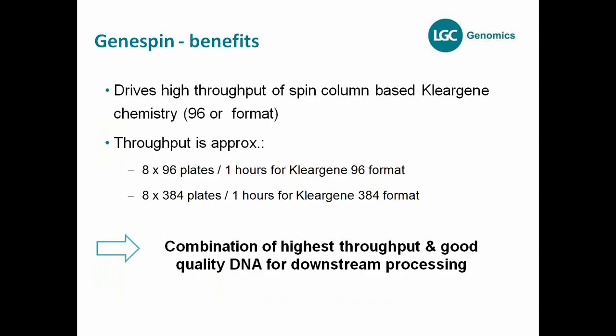Regarding throughput for the GeneSpin — it supports 384 and 96 formats. You can drive eight 96 plates in one hour for the Kleargene 96 format. And since there's essentially no difference in processing time between 96 and 384 plates, you can also run Kleargene 384 plates in one hour as well. We describe this as a combination of really high throughput and very good DNA quality. The GeneSpin and Kleargene system provides definitely very good quality DNA which you can use for most applications, but not all.